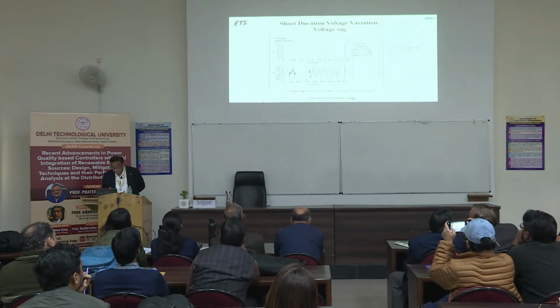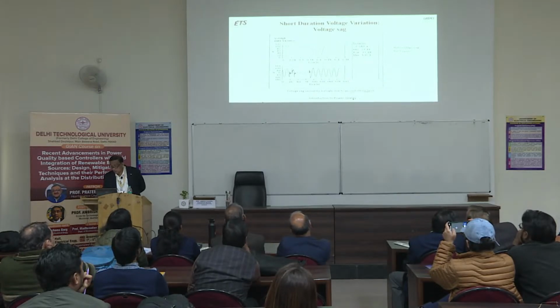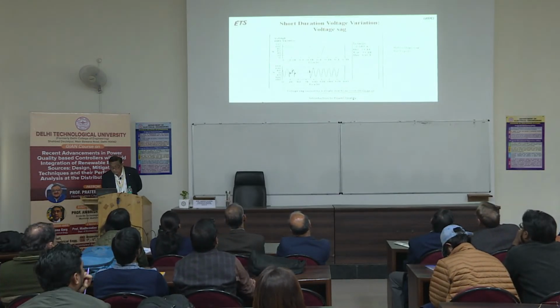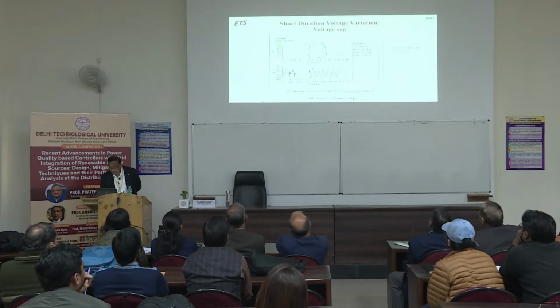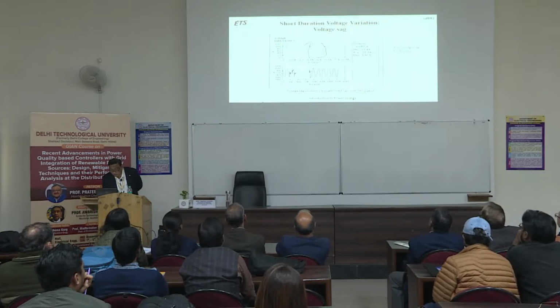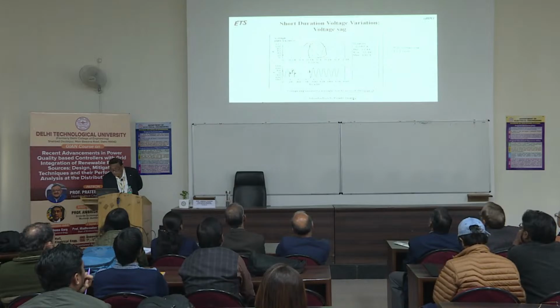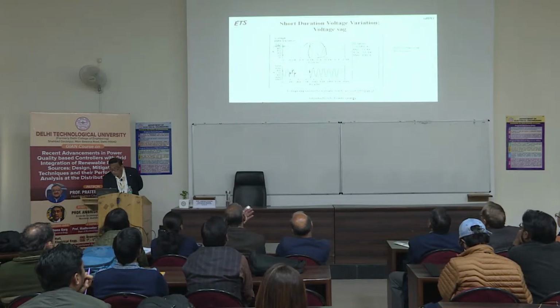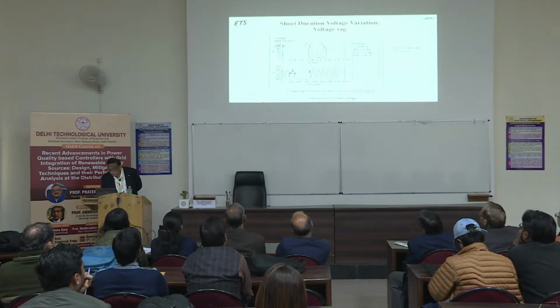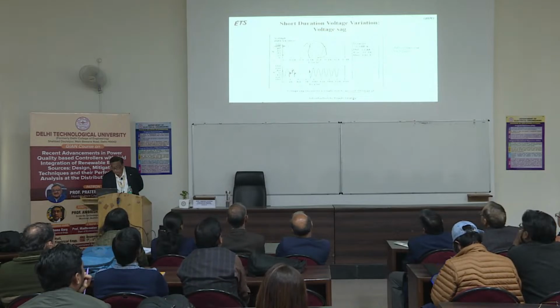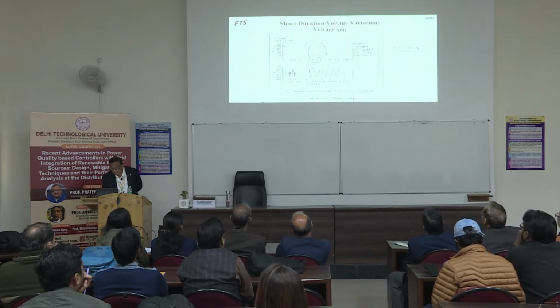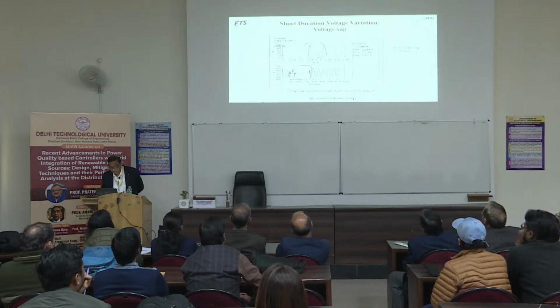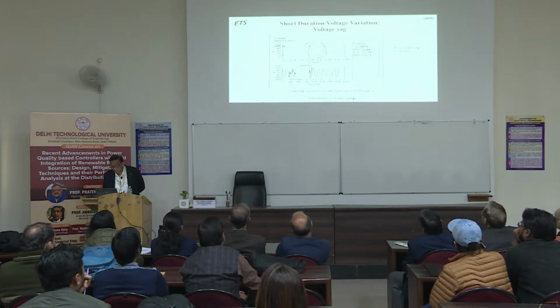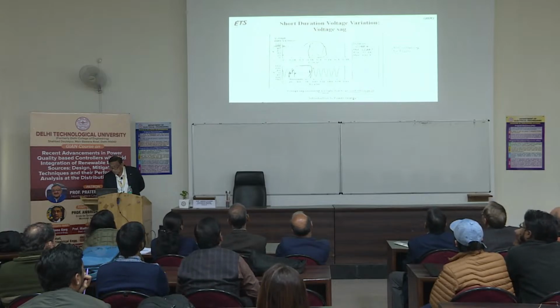So here you can see one example, voltage sag caused by a single line to ground fault. So you can see voltage sag, it's around 20% of voltage from around 100 volt. It came to minimum 17.44 volt. So it is around 80% voltage sag for around 3 cycles. So this is just an example of voltage sag caused by single line to ground fault.